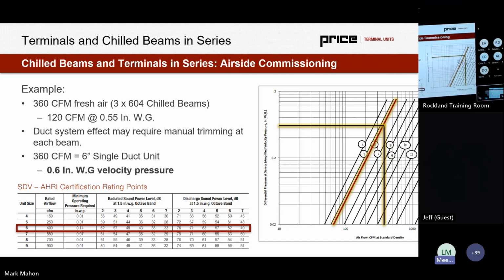And so when we look then at the calibration curves for a 6-inch single duct box, what we're going to see is 120 CFM, which I've kind of carved out on the screen here. We're looking at 0.6 inches of velocity pressure for that terminal unit as well. And that's 360, sorry. So these graphs are always confusing to read when we move from the x-axis to the right. Essentially, we're looking at a parabolic curve that's created and graphed linearly here, which is why it's kind of interesting to read. Takes me like at least 30 seconds to pick out points on this every time I look at it. I don't know why my brain hasn't figured it out yet, but so what we have here is 100 CFM, 200 CFM, 300 CFM, and then about 360.